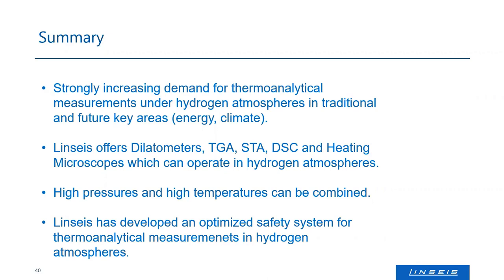There is one important question: it is sometimes not recommended to use platinum-based thermocouples in hydrogen. That is correct — you cannot use platinum thermocouples such as Type S for measurements in hydrogen. Type C is necessary, which uses tungsten and rhenium. You need to exchange the sample carriers for hydrogen measurement, as some instruments have the thermocouple integrated — for example, for the DSC you need to use Type C tungsten types, and for the dilatometers the integrated thermocouple must be exchanged when measuring in hydrogen.